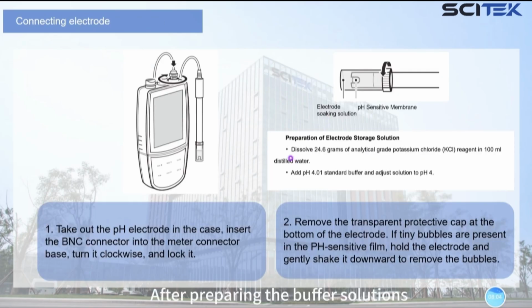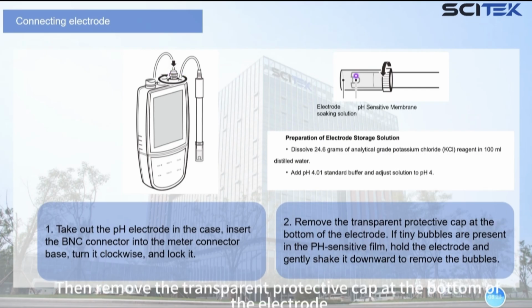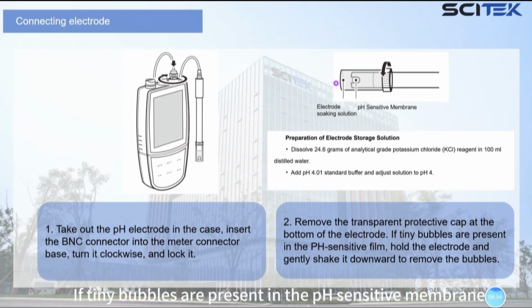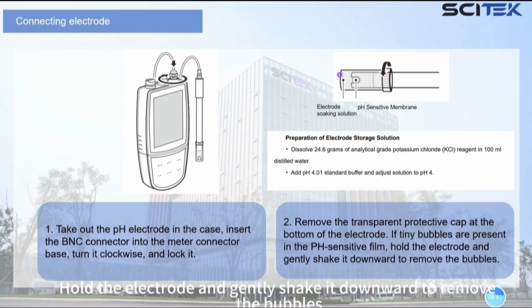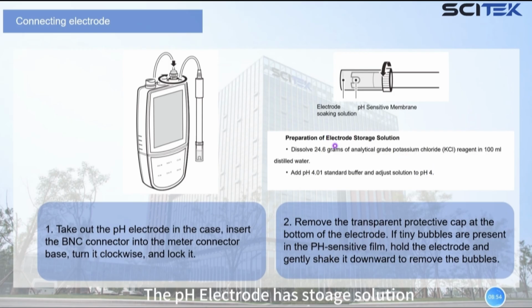After preparing the buffer solutions, we connect the electrode. For the pH electrode, insert the BNC connector into the socket. Rotate and push the connector clockwise until it locks. Then remove the transparent protective cap at the bottom of the electrode. If tiny bubbles are present on the pH-sensitive membrane, hold the electrode and gently shake it downward to remove the bubbles. The pH electrode has storage solution. You can prepare the solution according to this method.